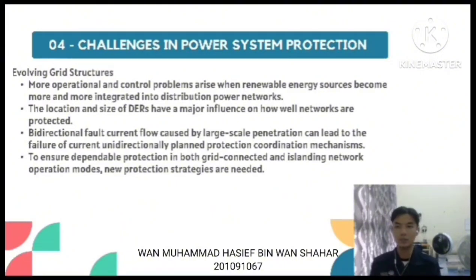Okay, thirdly, evolving grid structures. More operational and control problems arise when renewable energy sources become more and more integrated into distribution power networks. The location and size of DERs have a major influence on how well networks are protected. Bidirectional fault current flow caused by large-scale penetration can lead to the failure of the current unidirectionally planned protection coordination mechanism. To ensure dependable protection in both grid-connected and islanding network operation modes, new protection strategies are needed.